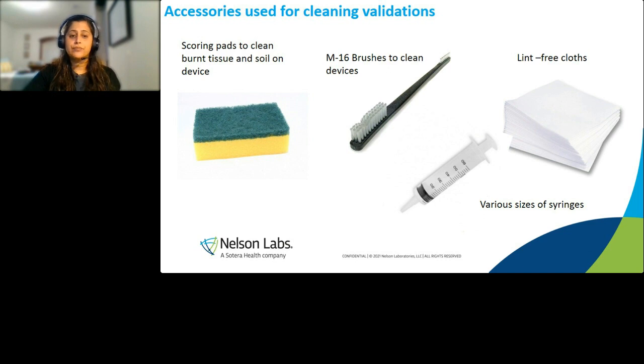Syringes, brushes, scoring pads. The scoring pad is only used if there have been electrosurgical procedures where the test soil has baked on the ends, where you can't get it off with a brush no matter how many times you soak it. So you need the help of a scoring brush. These are also not an all-the-time thing we do. This is only used if the manufacturers specify it in their IFU. So a lot of the supplies are driven by the IFU.